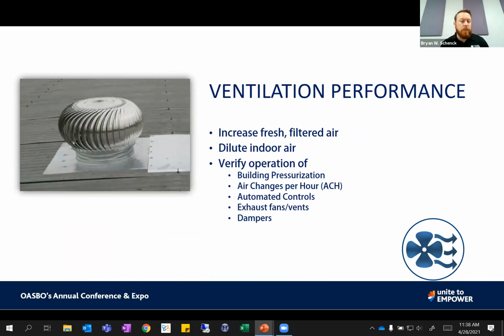So ventilation performance - when it comes to medical professionals right now, they say bring in as much outdoor air as you can, but it's very critical that it's filtered outdoor air. Opening windows should be a last resort, because we don't want to affect how that air comes in and affect energy performance and the comfort of our facilities. If we open windows, we might bring in more outdoor air, but we also might bring in a lot more pollutants - from a crop field next door, or a construction site next door - and that could be bad in other ways. So we want to make sure we bring in filtered outdoor air through our mechanical systems wherever possible. The intent is to dilute the indoor air with fresh outdoor air, and that actually has a cleaning process to it as well.